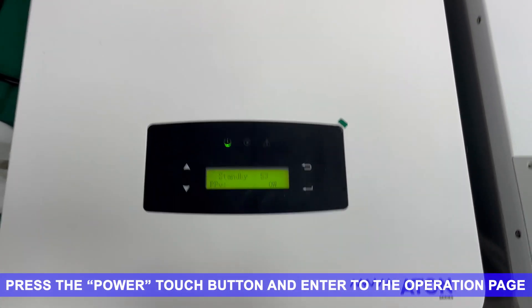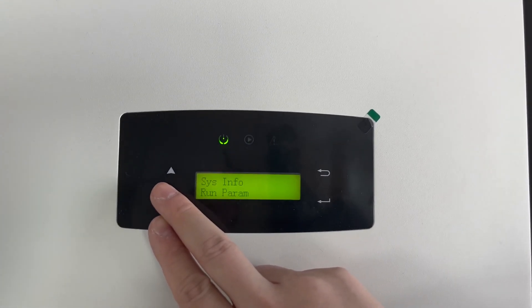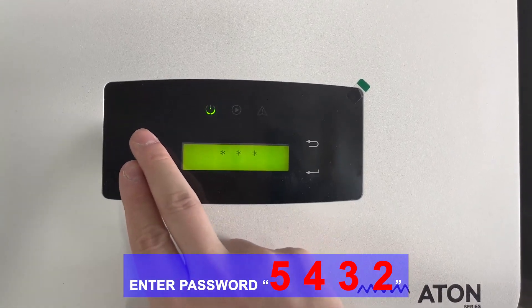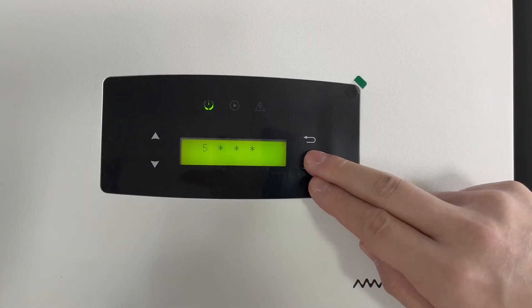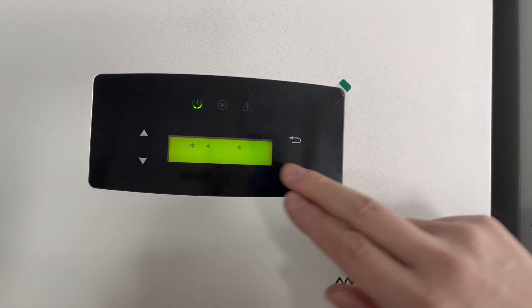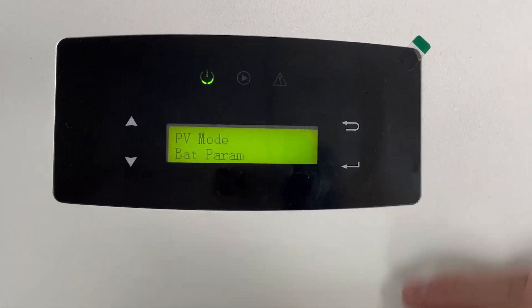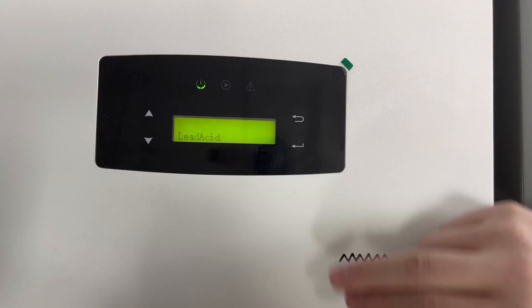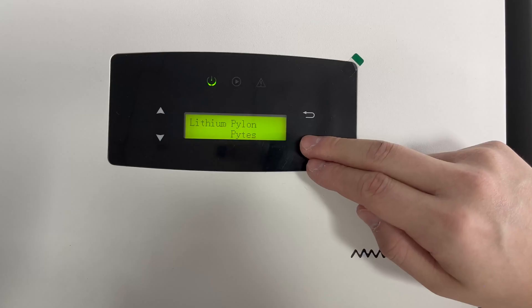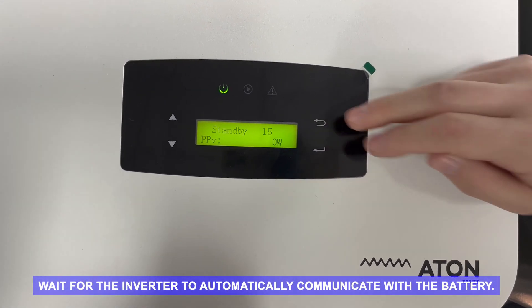Press the power touch button and enter the operation page. Select Run Parameter. Enter password 5-4-3-2. Select BatParam. Choose Lithium and Pylon Protocol. Press the back touch button to exit. Wait for the inverter to automatically communicate with the battery.